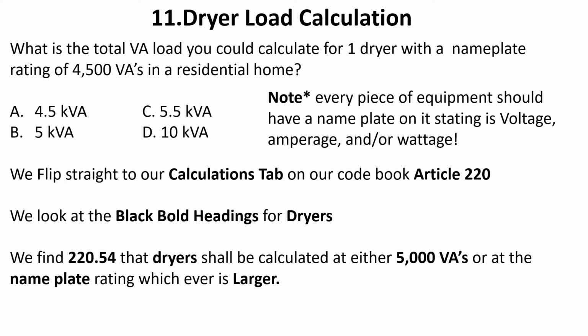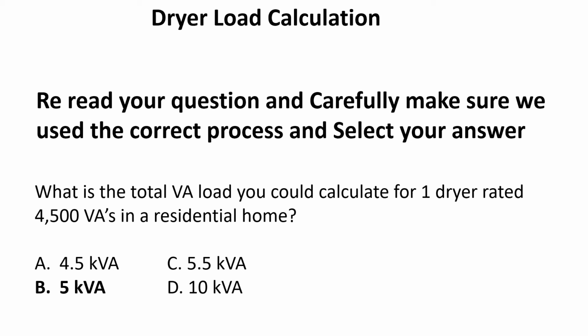We find that in 220.54 dryers shall be calculated at either 5,000 VAs or at the nameplate rating, whichever is larger. So it's a 5,000 minimum or the nameplate rating, whichever is larger, and you'll use that for your load calculation.